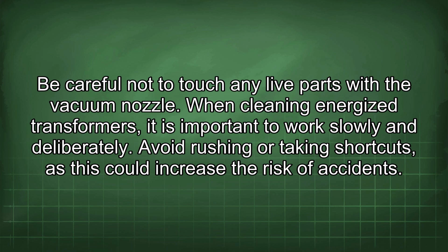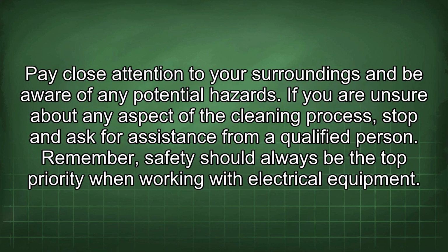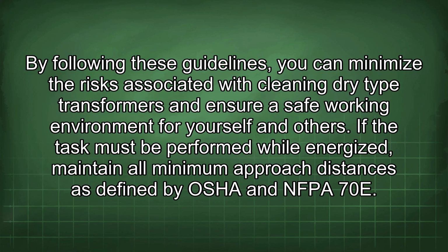When cleaning energized transformers, it is important to work slowly and deliberately. Avoid rushing or taking shortcuts, as this could increase the risk of accidents. Pay close attention to your surroundings and be aware of any potential hazards. If you are unsure about any aspect of the cleaning process, stop and ask for assistance from a qualified person. Remember, safety should always be the top priority when working with electrical equipment.